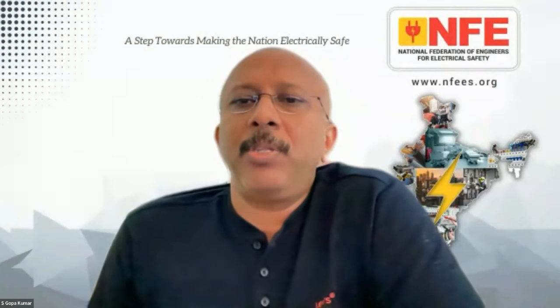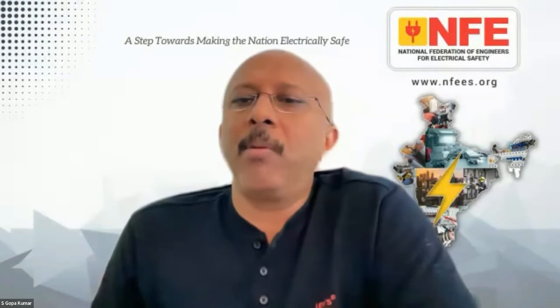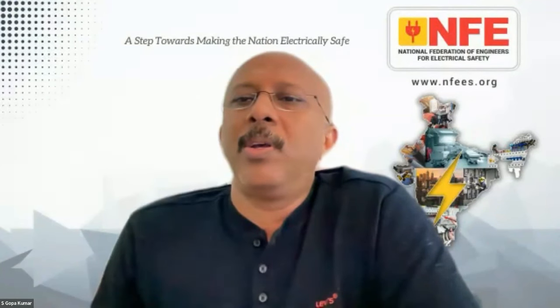So the next question from Mr. Sanjay Mulai: in case of a TNCS system, if the neutral is broken, then what is the protection to avoid overvoltage in the distribution system? So as I said, at the moment, the go-to thing in England is these OPDD devices, open PEN detection devices, which seem to be the great next hope to mitigate that. The bigger debate there is the lack of product standards at the moment for it, the risk of introducing any new technology, its performance, obviously. And also there's a bigger question of, why are we mitigating for the supplier's failure? Why does the homeowner have to pay because the electricity network that you pay your money to in your bill hasn't maintained the network?